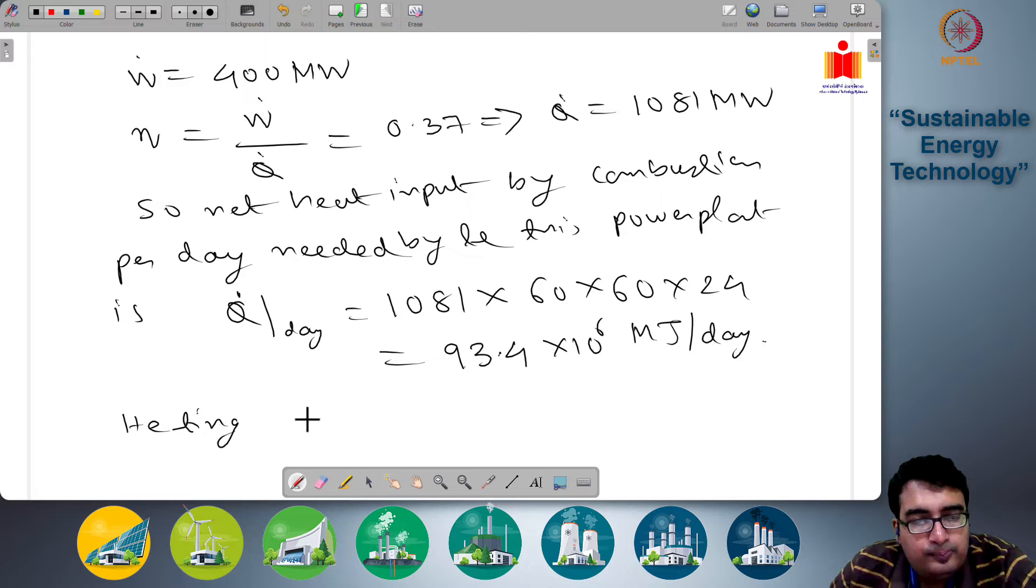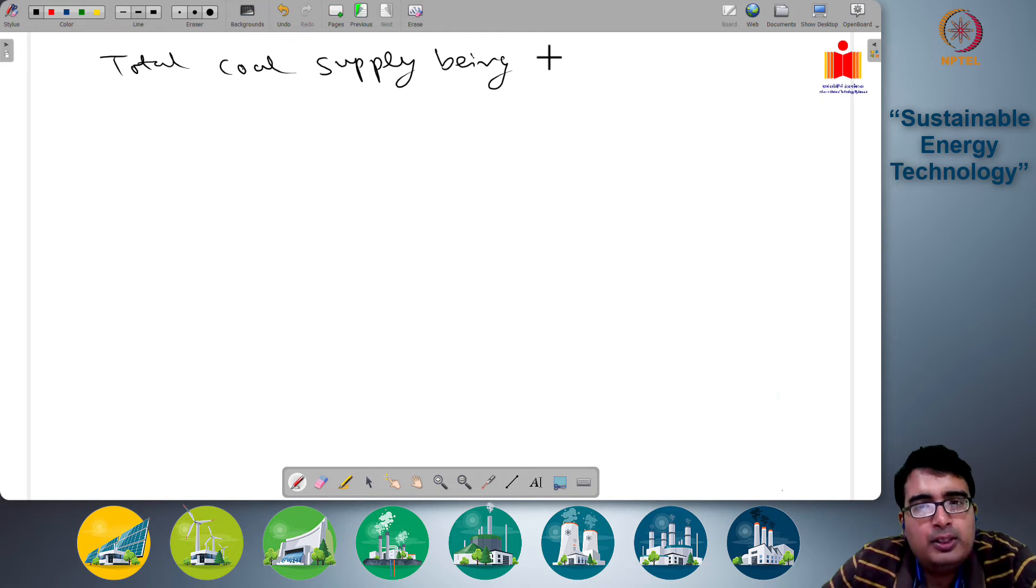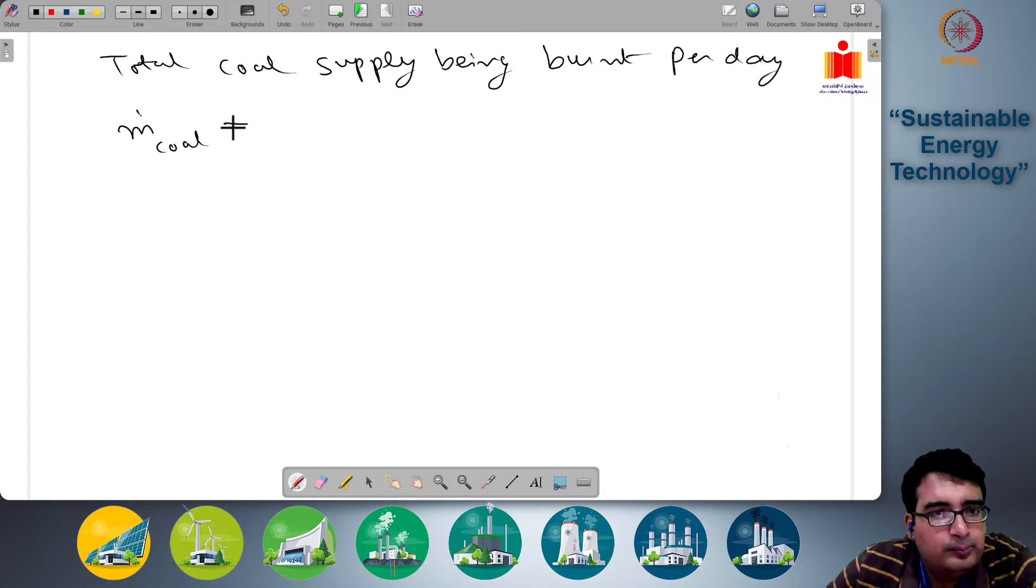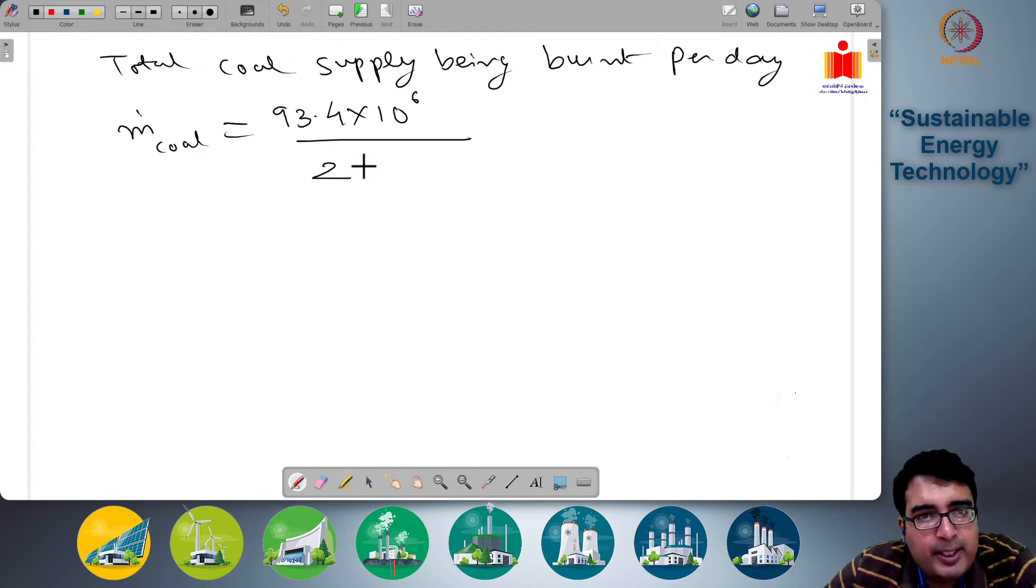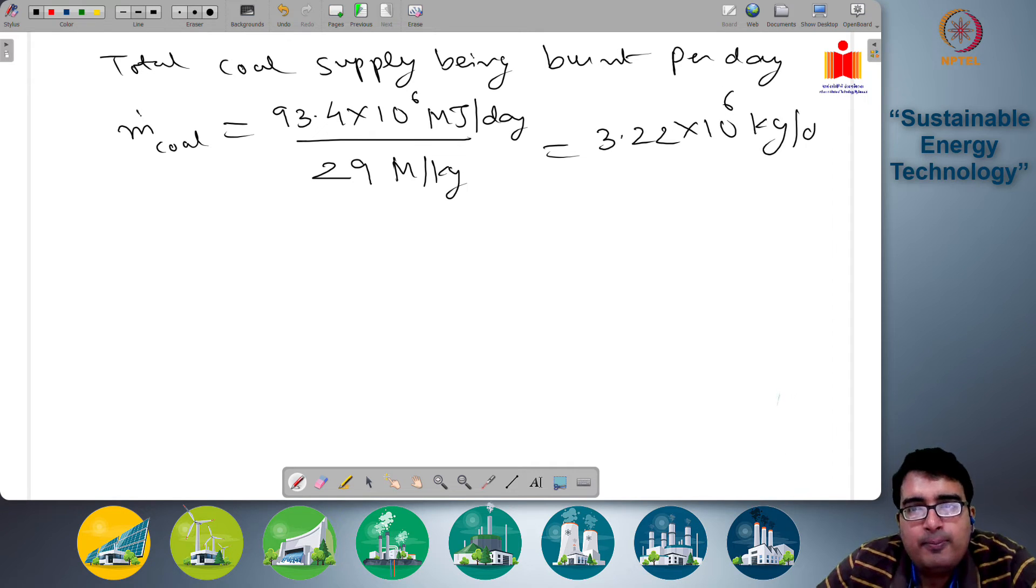Heating value of coal is 29 megajoules per kg. So total coal supply being burnt per day, m dot coal, is the amount of heat required, 93.4 × 10^6 megajoules per day, divided by 29 megajoules per kg. So this is megajoules per day, this is megajoules per kg, which gives you 3.22 × 10^6 kg per day of coal.